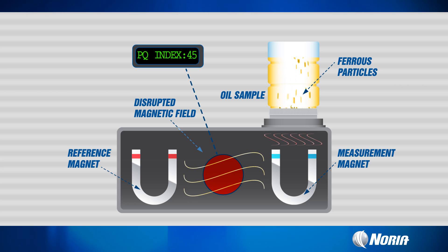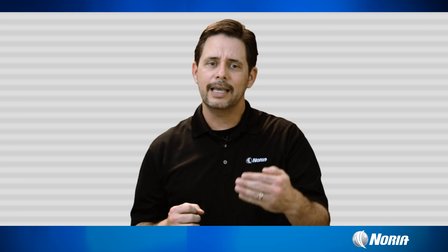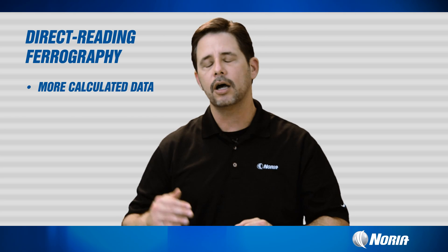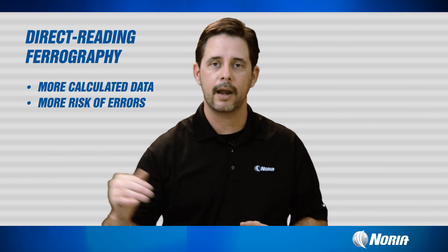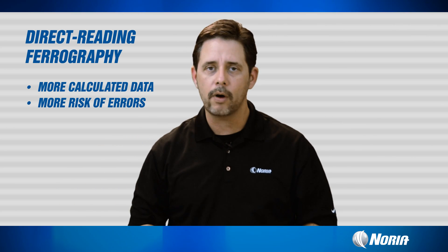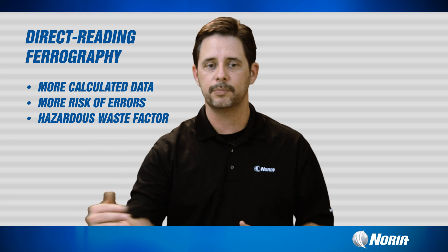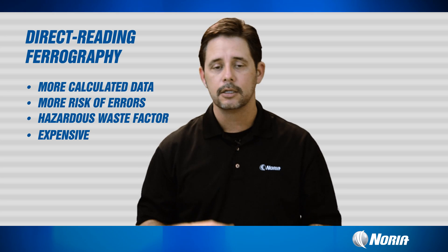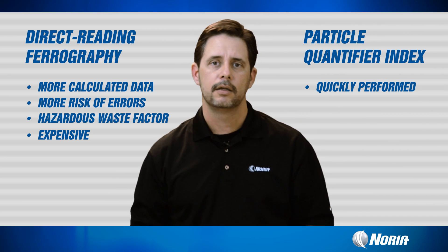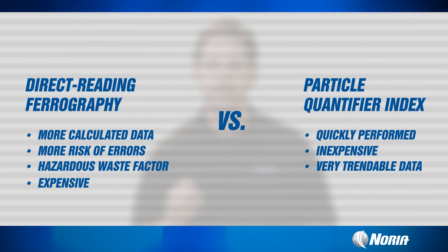The PQ index is a very trendable, easy number to work with. With DR ferrography we have more calculated data, but with that comes the potential for sample prep error, plus hazardous waste disposal requirements, making DR ferrography a much more expensive test. The PQ index, on the other hand, is very quick, very inexpensive, highly trendable, repeatable, and reproducible, with virtually zero sample prep and very little potential for technician error.